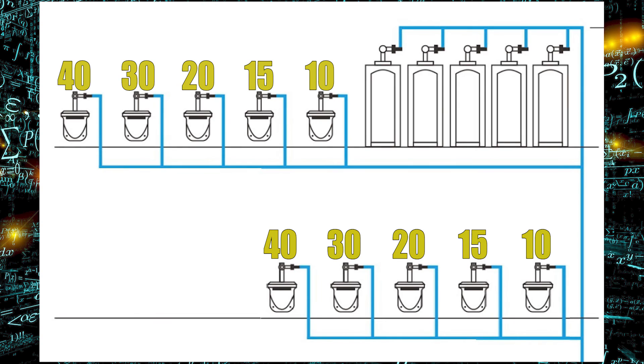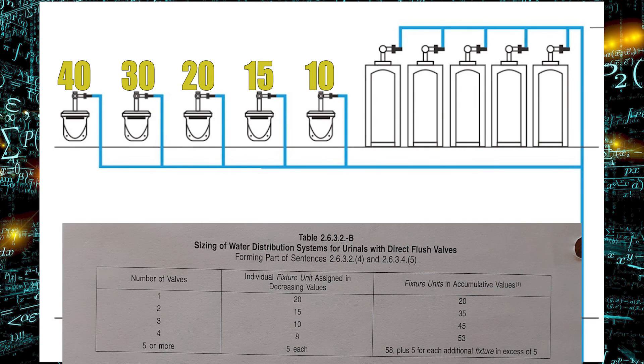Now the urinals up top though, we need to look at table 2632B. So this one on the far left is going to be 20 fixture units, the next one is 15, the next one is 10, the next one is 8, and the last one is five.